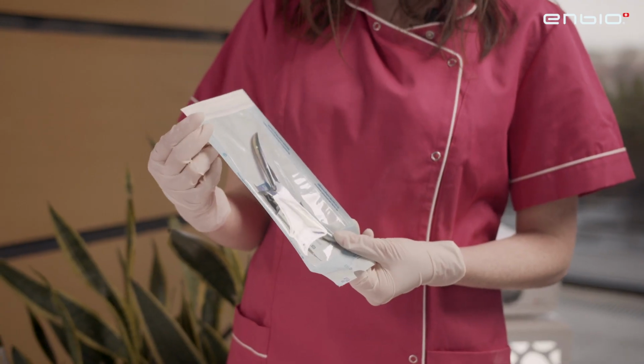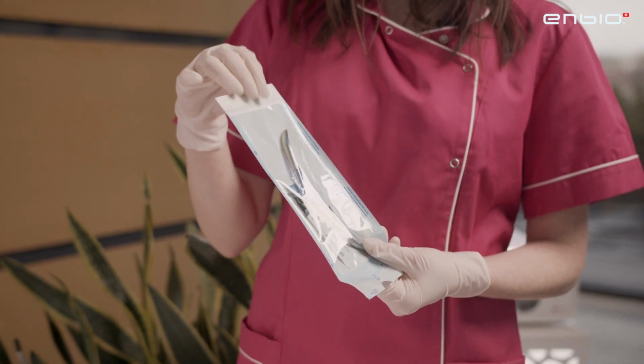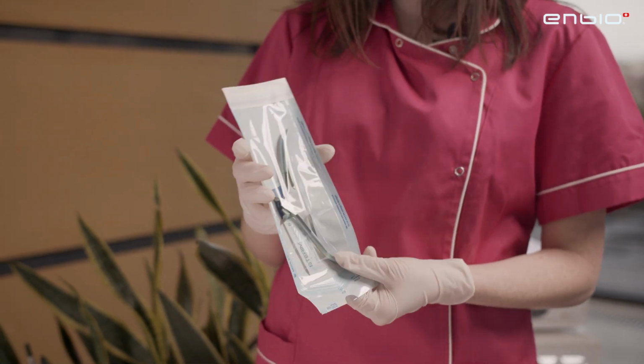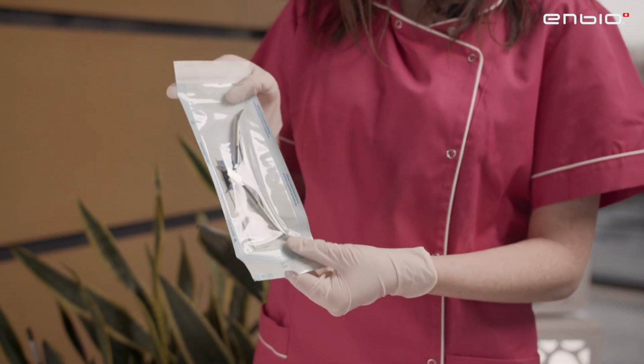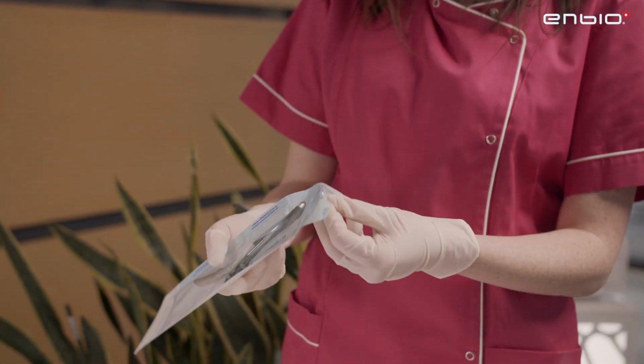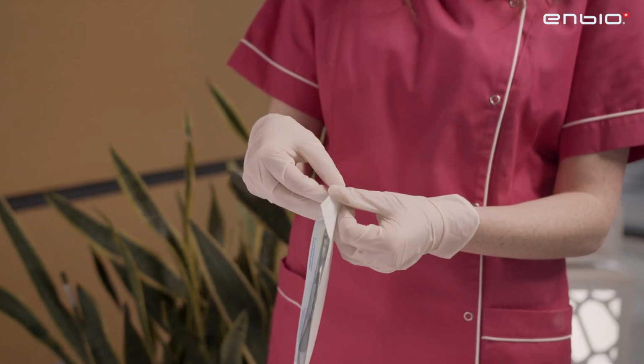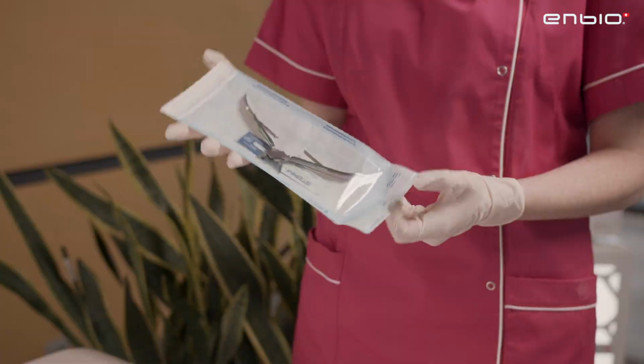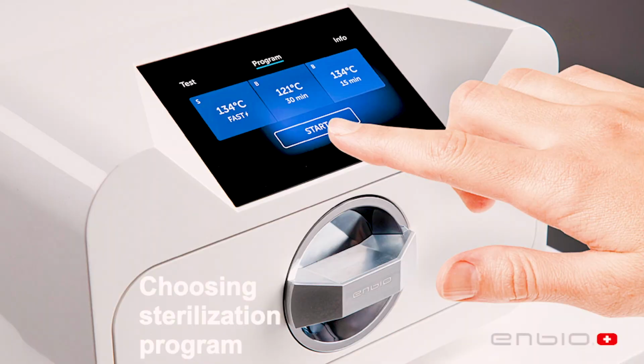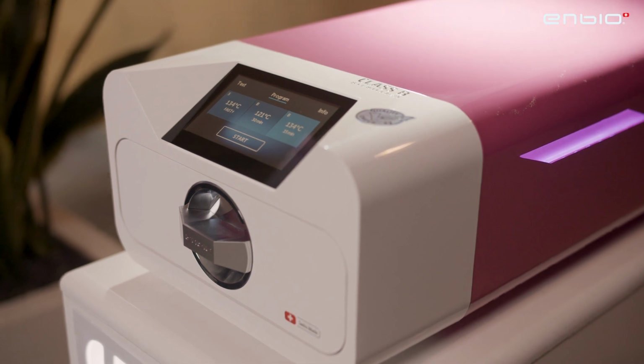So we have sealed the sterilization pouch here, but after we take the tool out of the autoclave, when we are trying to open the package, we have to do it on the other side. So we will open the sterilization pouch from this part here. It is important to know that there are 3 classes of sterilization: Class N, which is the lower one, Class S, which is the middle one, and Class B, which is the best class because it can sterilize all kinds of tools. Let's see how we should put the tools inside the autoclave.